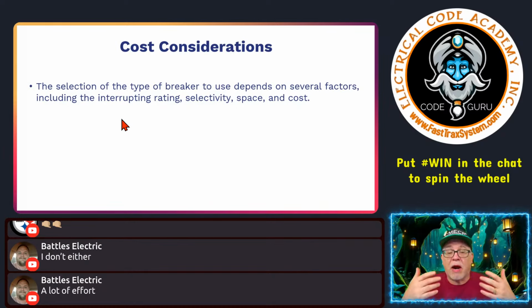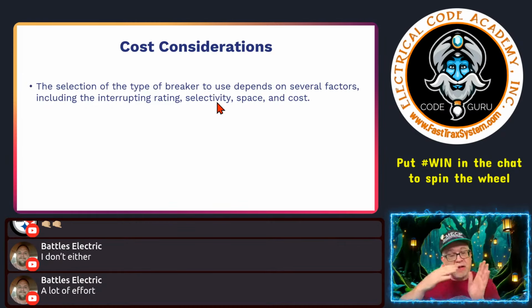Now we have that required at a lot more places now than just services. So be aware of that in the NEC. A lot more places have a requirement to show the available fault current at a piece of equipment so that it doesn't blow up in your face, okay? Selectivity. Again, you might have to choose certain breakers, certain trip curves, certain applications based on the need for selective coordination. You may not need selective coordination, okay? But if you do, then you'll need to understand that that could affect the cost of your breaker.